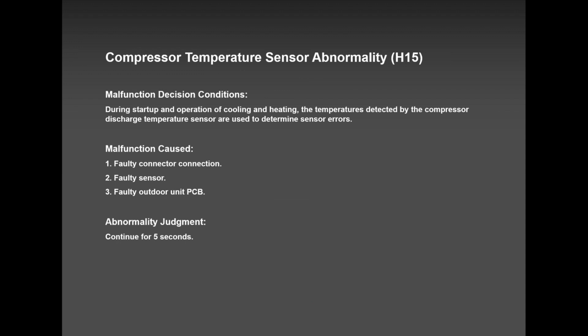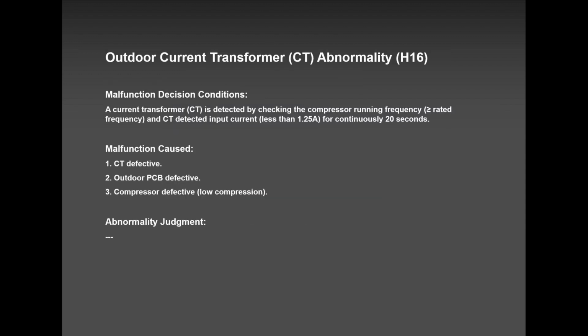H15, I have never seen this error code, but it can happen. And if you have this error code, this is how you troubleshoot it. H16, I had 2 or a maximum of 3. The pumping of the compressor was not powerful enough. So they replaced the compressor and everything went back up and running.